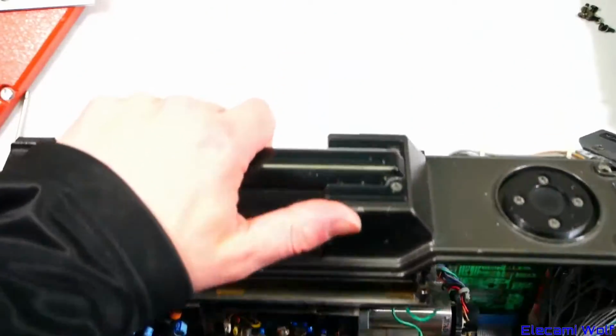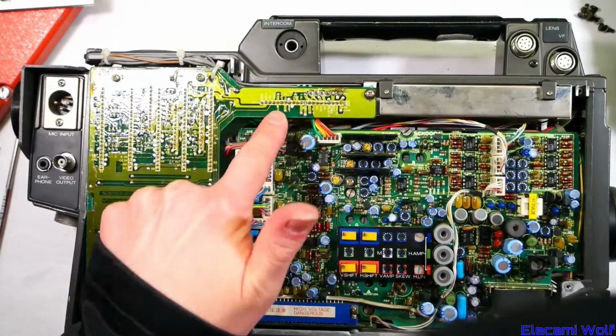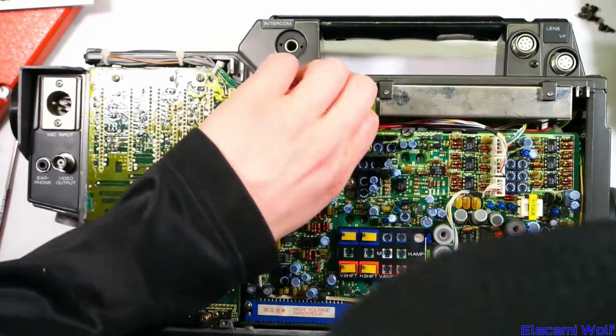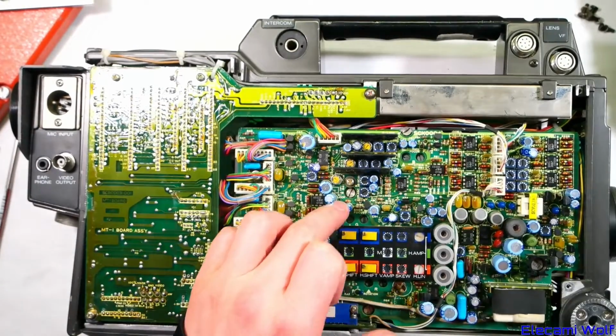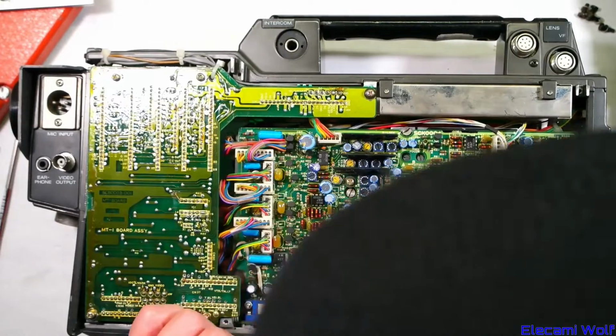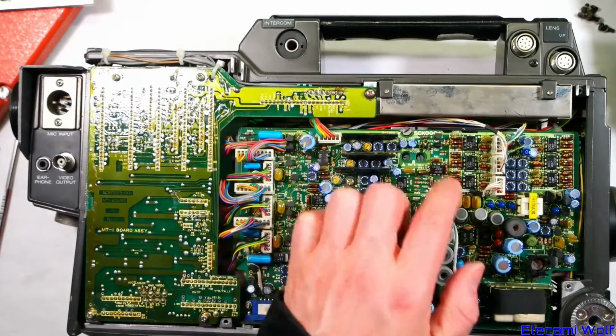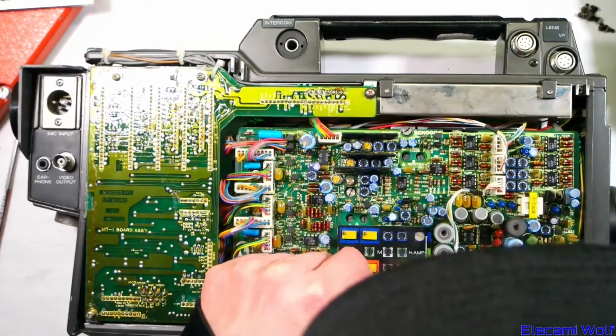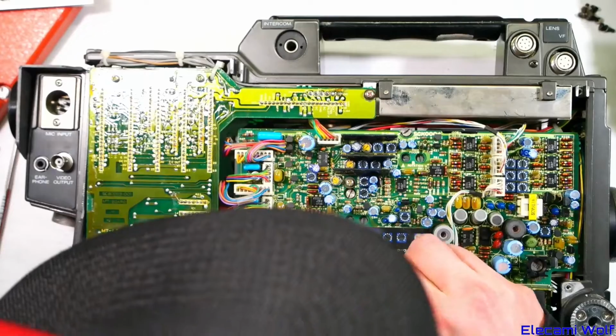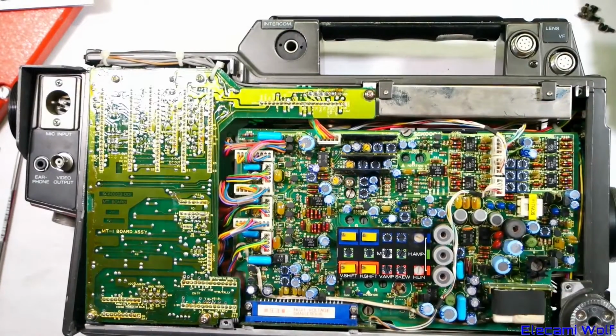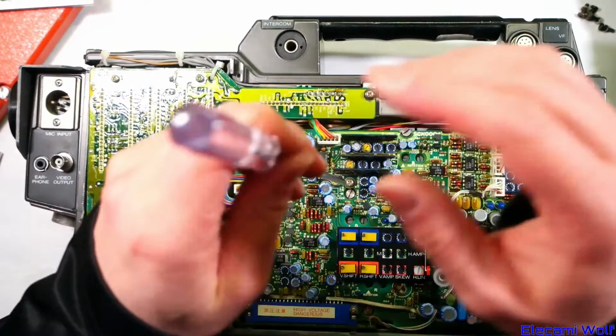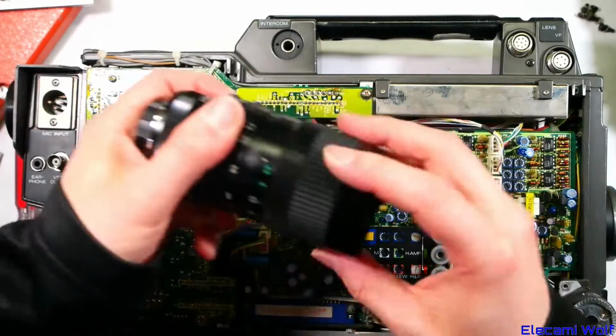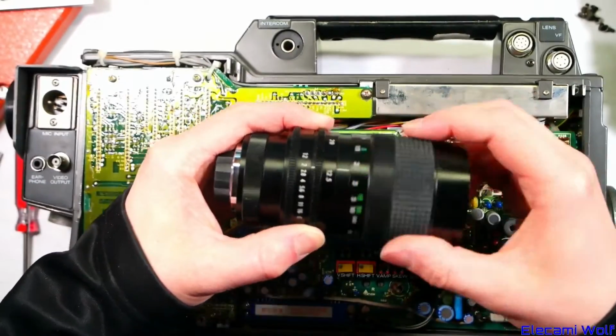Okay, let's check out the other side. Oh yes, the sync gen plugs into that connector there. Now I wonder if we can get this out so we can have a look behind it. There's holes through it for adjustment screws. Oh, it's back focus. Rotation and back focus for the tubes. And what is that other one? Says there. R lock. G lock. B lock. Okay, so that locks the tubes in place, and the 2 is for rotation and back focus, like the distance of the face of the tube to the lenses, so that you can calibrate it to have these markings on the lens for the focus distance actually correlate with real measurements.